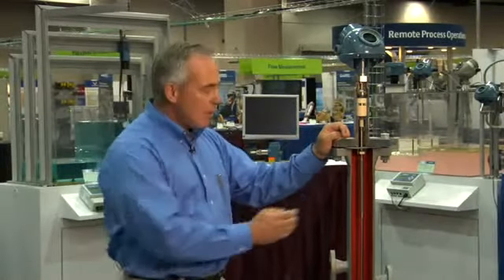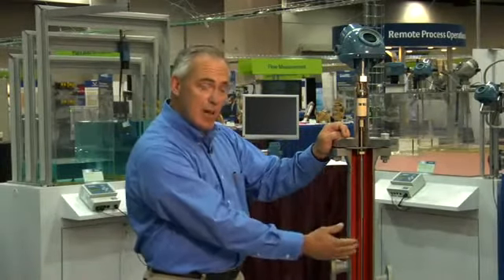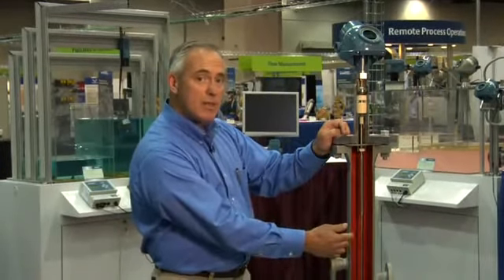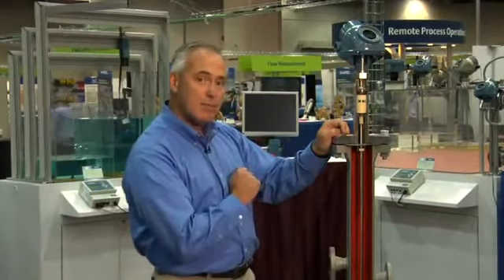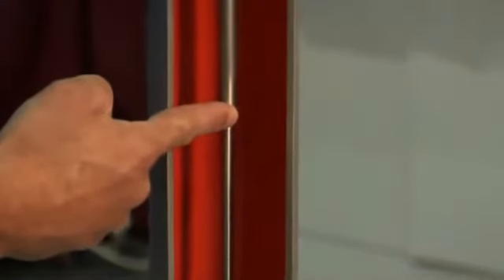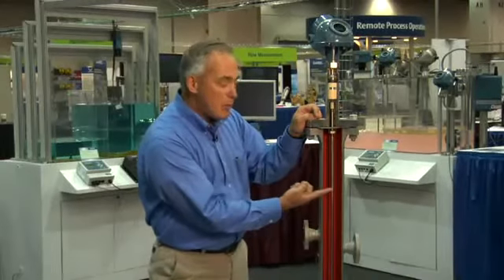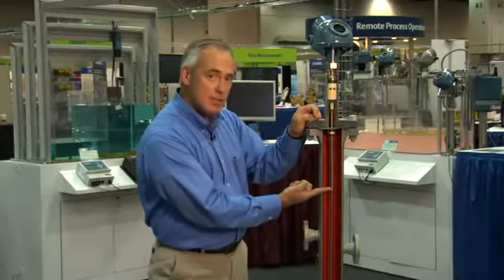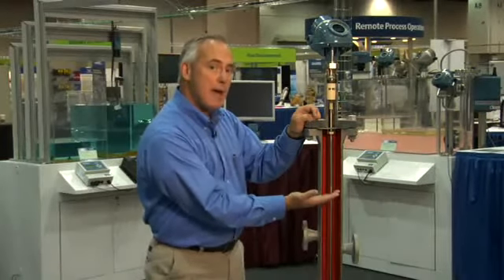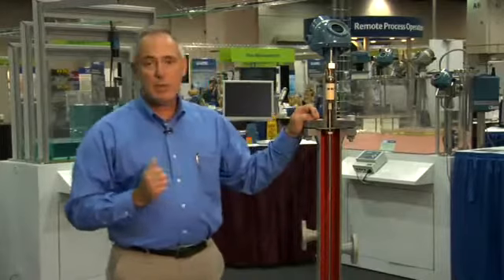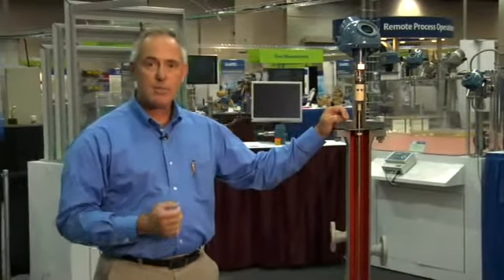The trouble is that when you have saturated steam in this area above your level, the steam will actually affect the speed of the microwave. So if you don't know how fast your microwave is going, we really can't make a good level measurement on that product. So what we do is we put a reflector on this probe at a known distance, so that when we send that microwave out, we know that this is at a certain distance, and then we scale the whole measurement back to that known distance. So we can make an accurate level measurement under all types of varying conditions, from ambient conditions to full bore run rates.